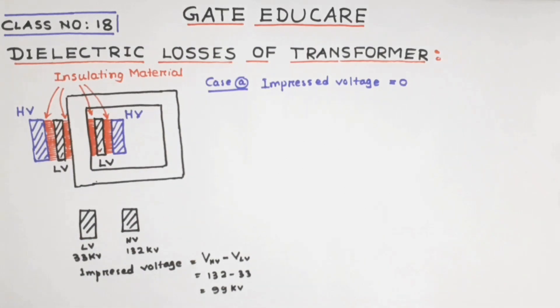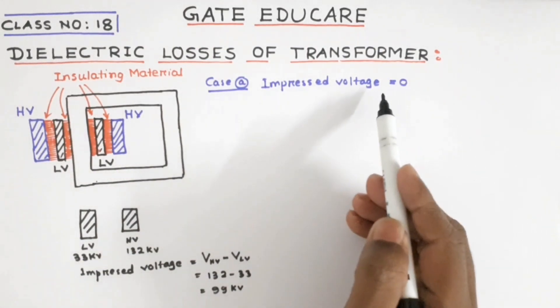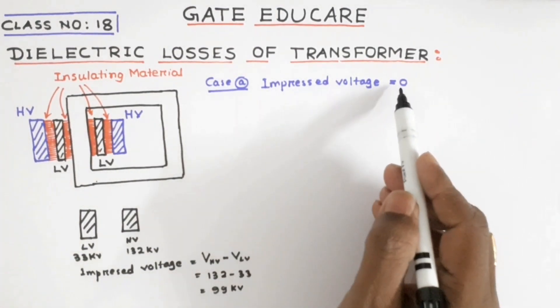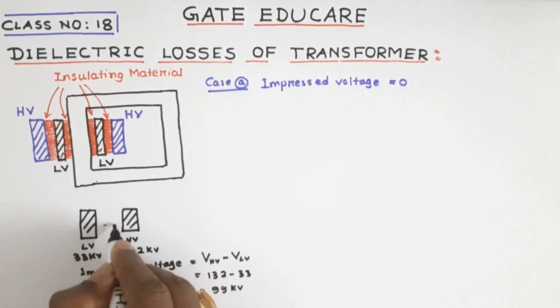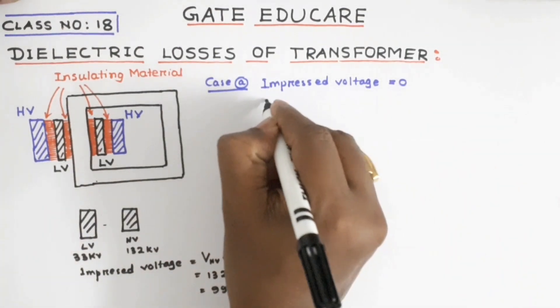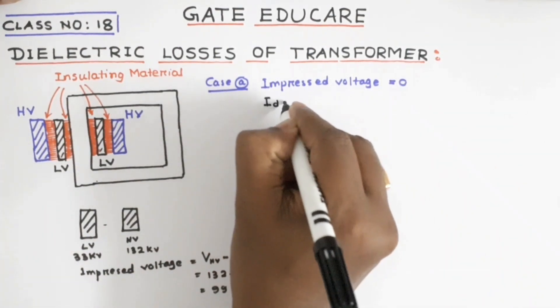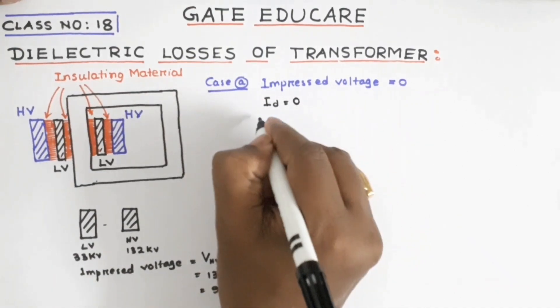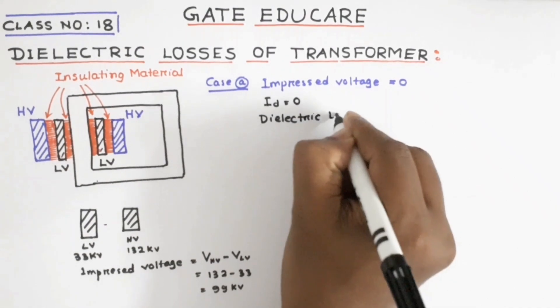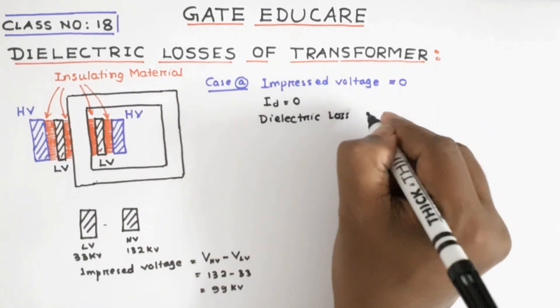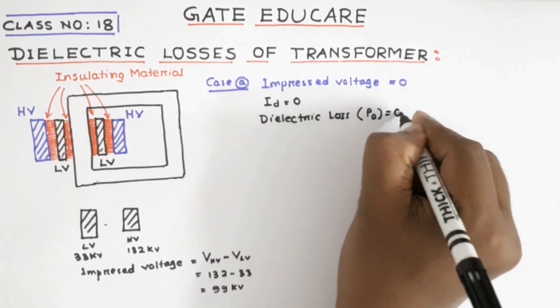Now consider Case A. Here the impressed voltage is zero, meaning the low voltage and high voltage winding have the same potential — there is no voltage difference, so the impressed voltage will be zero. In this case, there is no current between the insulating material. Therefore, the displacement current ID between the insulating material is equal to zero, and the dielectric loss PD is also equal to zero.